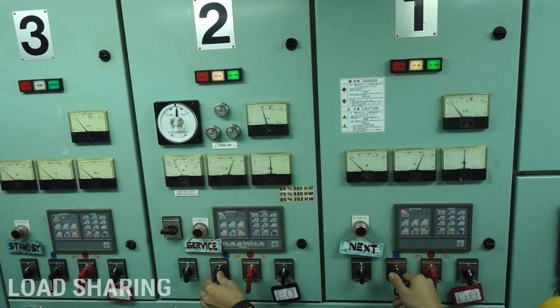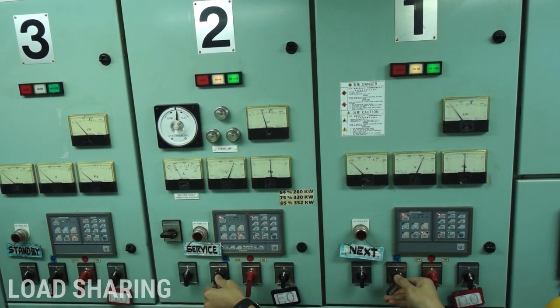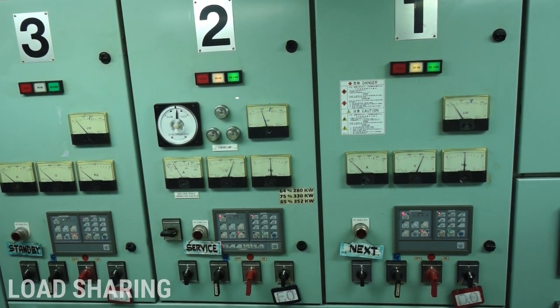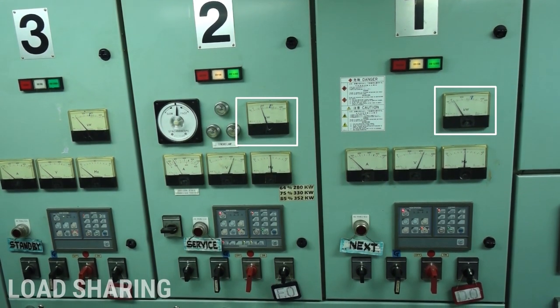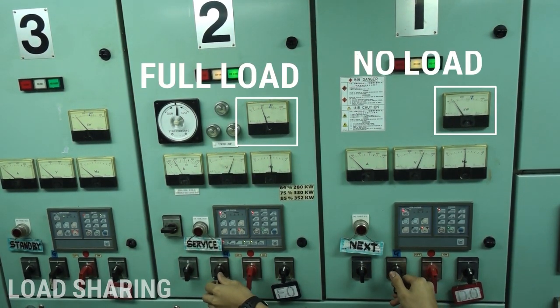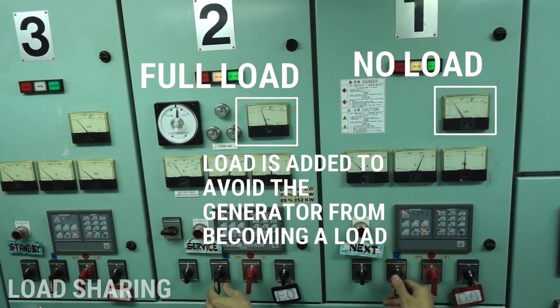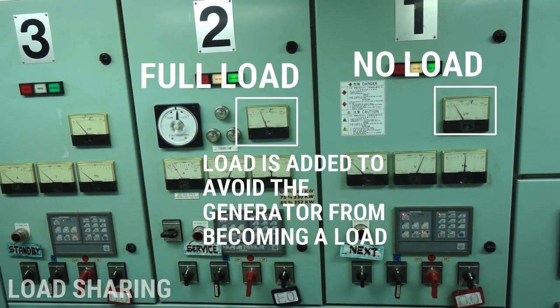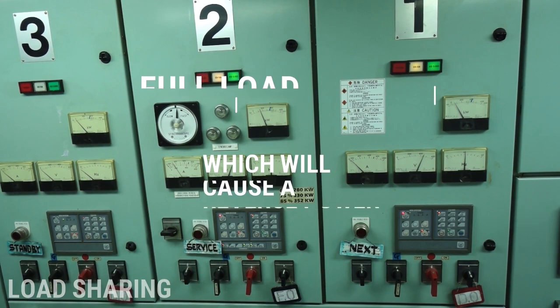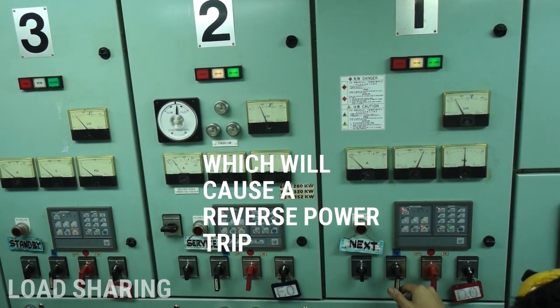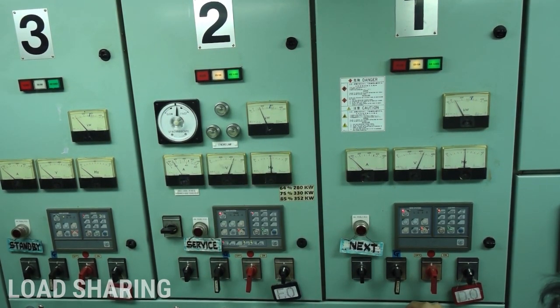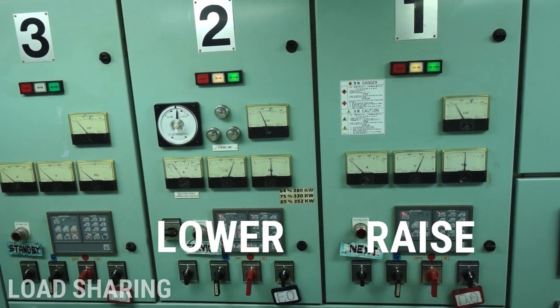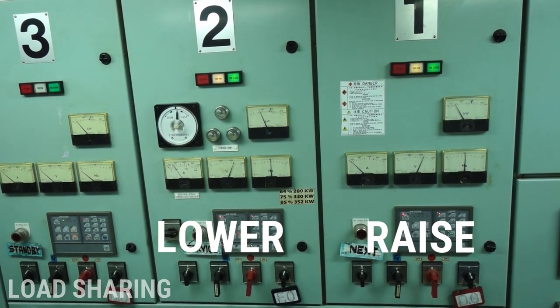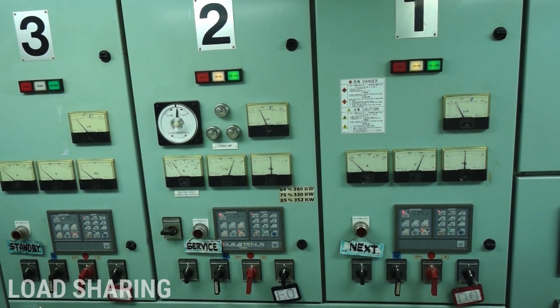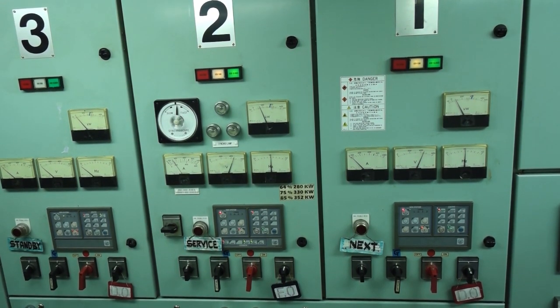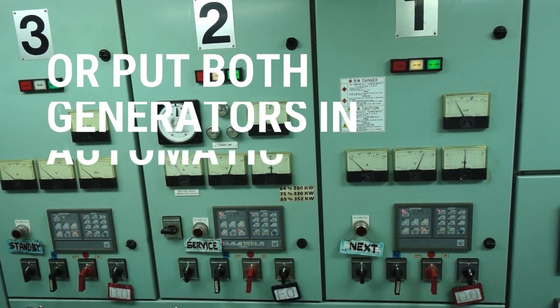The final step is load sharing. Once the circuit breaker is closed, the generators are already running in parallel, with one running at full load and the other without load. Load is added to the newly connected generator. This is to avoid it from becoming a motor, which will cause a reverse power trip. Load is also subtracted from the other generator. This is to maintain the system's frequency. Continue to add and subtract load until the desired load share is reached.